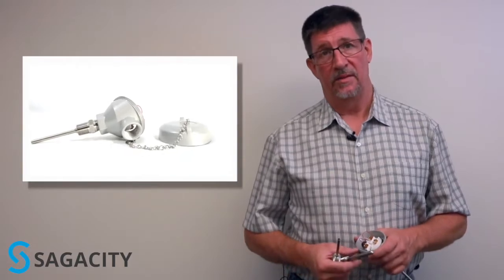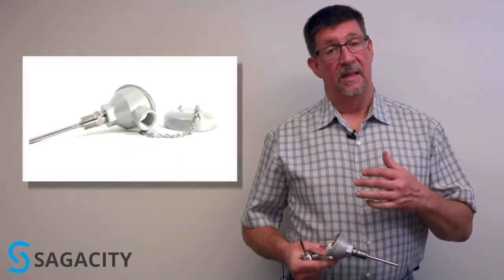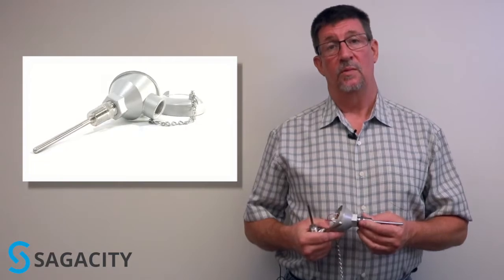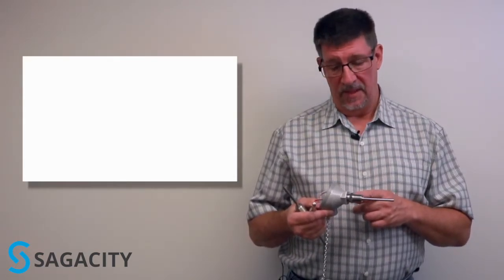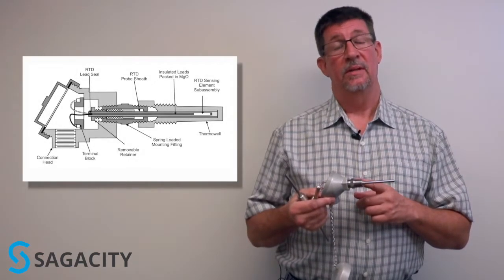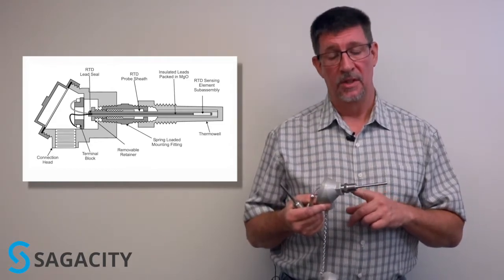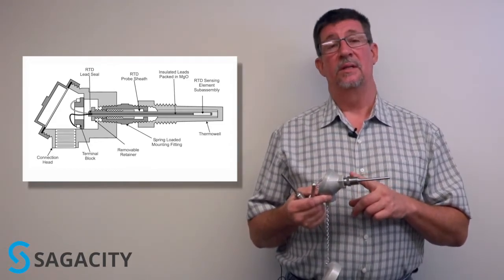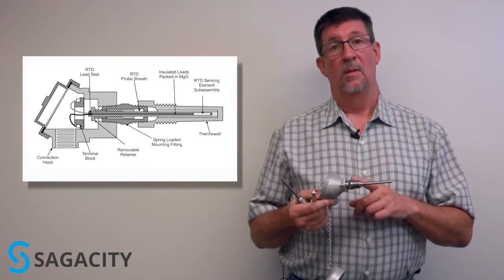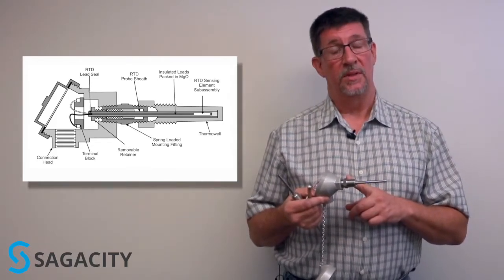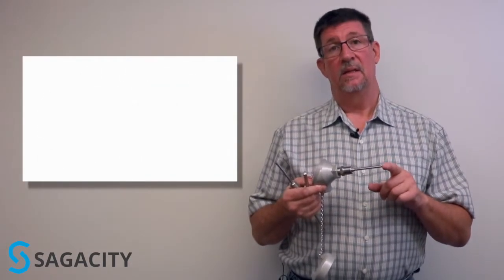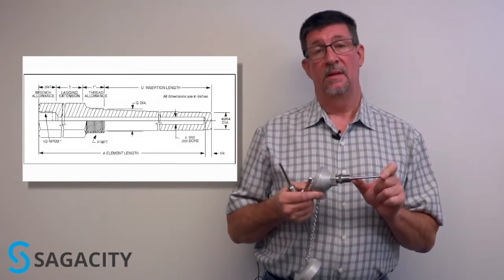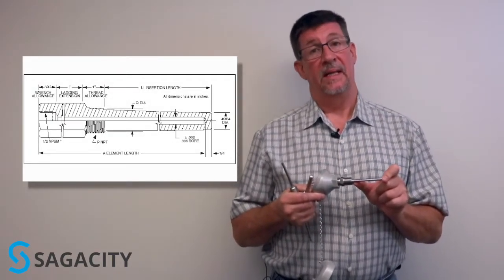When you're specifying an RTD or thermocouple, again keeping in mind that you'll probably interface that device with a thermal well which we're going to cover in another video, but you will want to know how you're going to connect to that thermal well. The most common is a threaded connection. This particular one is a half inch. You may have three quarter inch but typically you're going to thread this into your thermal well. This is your process connection as far as the RTD or thermocouple is concerned. The distance between the bottom of that and the end is your stem length or u-length and that's typically determined by the length of your thermal well.